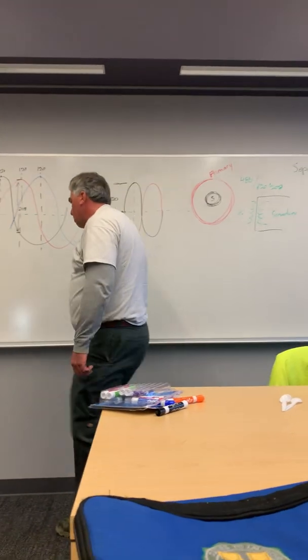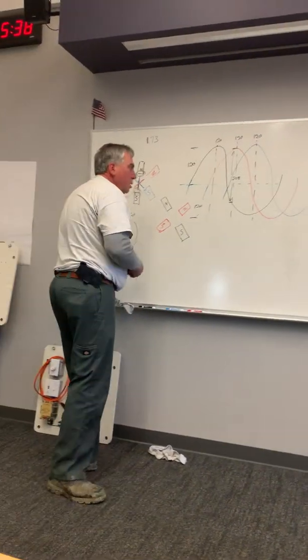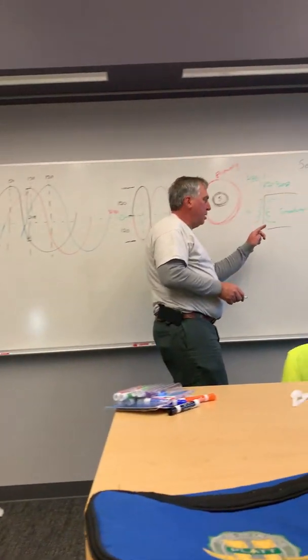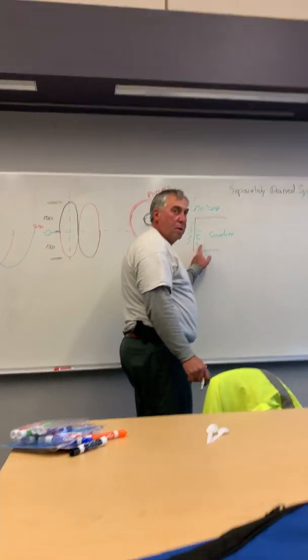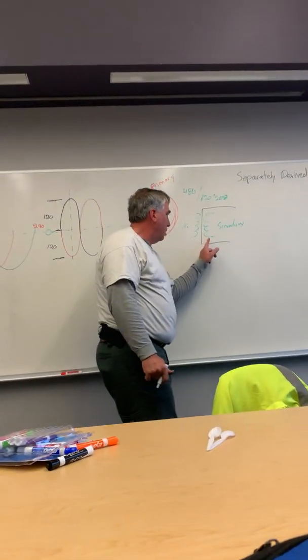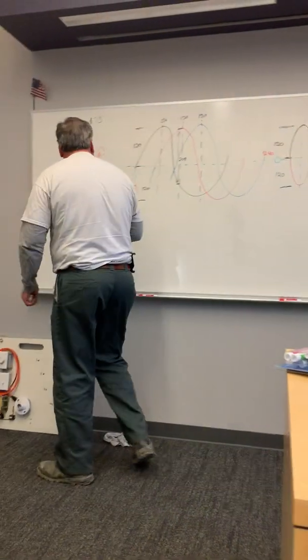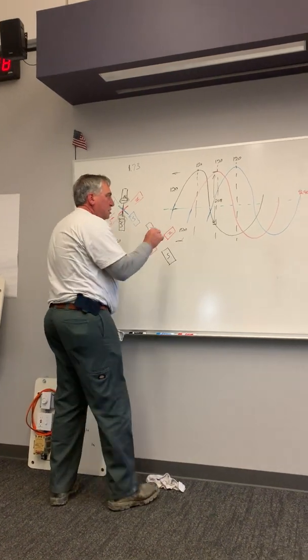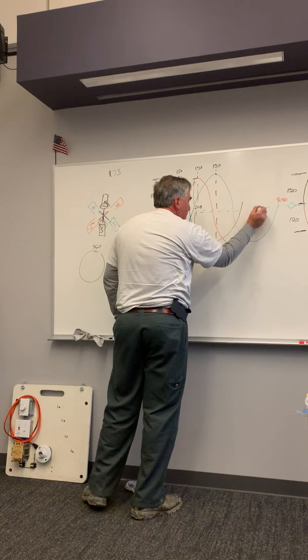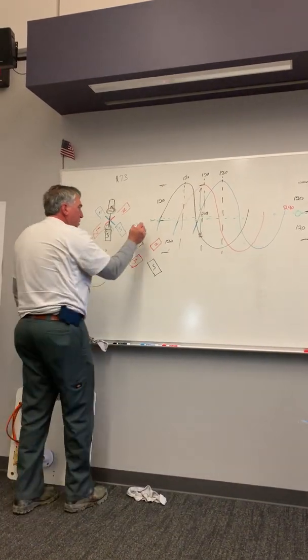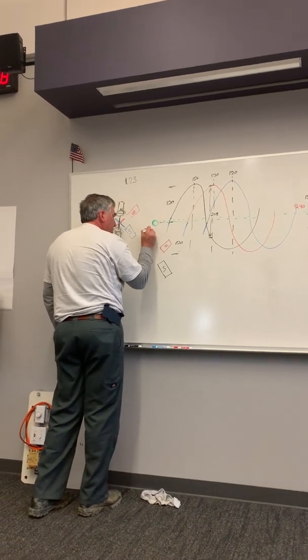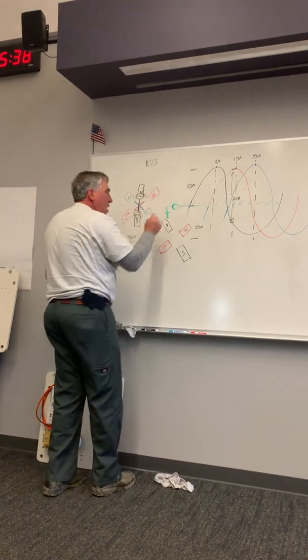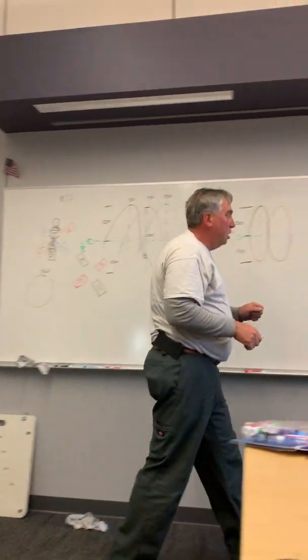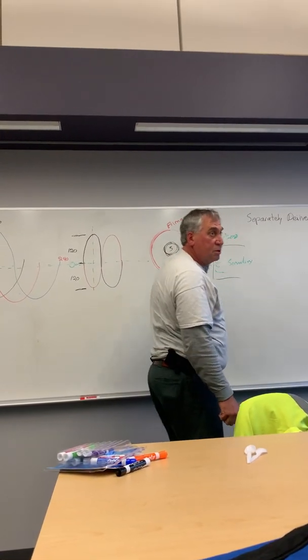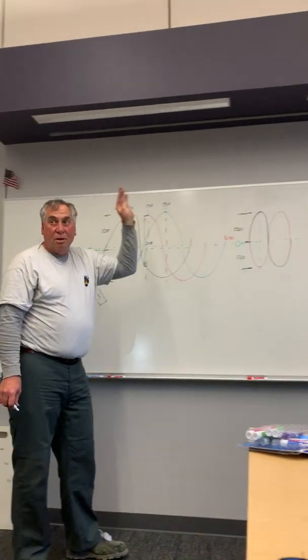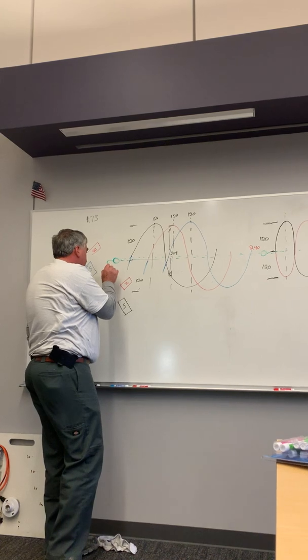Now let's talk about the separately derived system. You're having to create your own power here, so there's a couple of responsibilities that you have to have. One thing I like to talk about is going back to the zero reference I mentioned earlier. The zero reference is basically where we're going to ground, and we tie that in whenever we create a new system, or if you have a service coming in from the building, coming in from PG&E, you establish this ground.